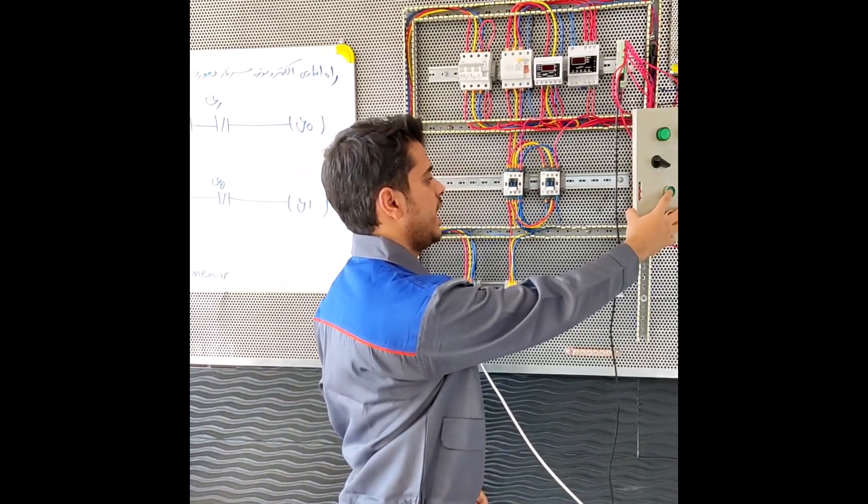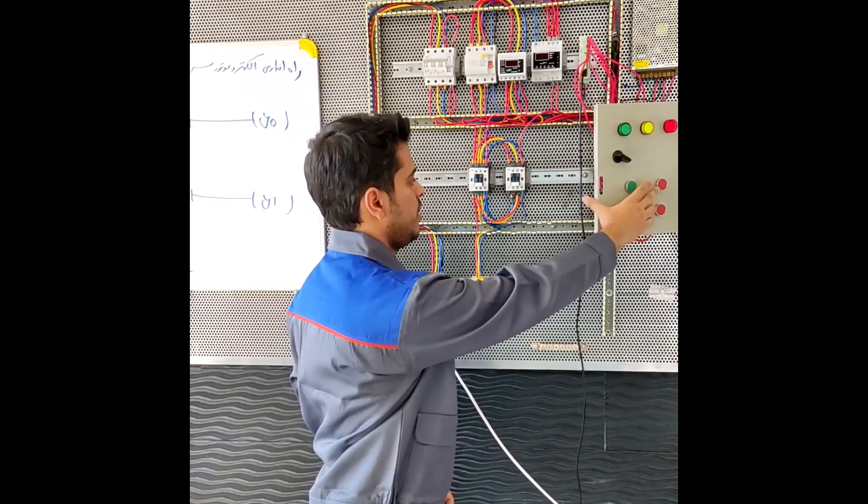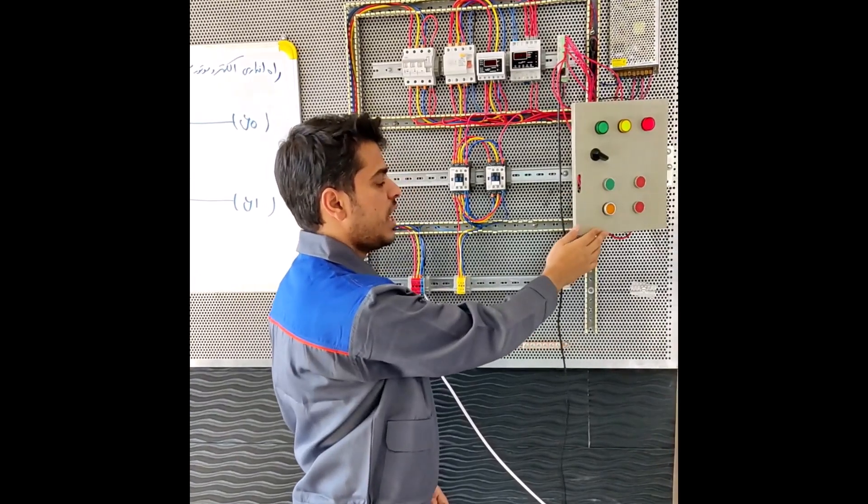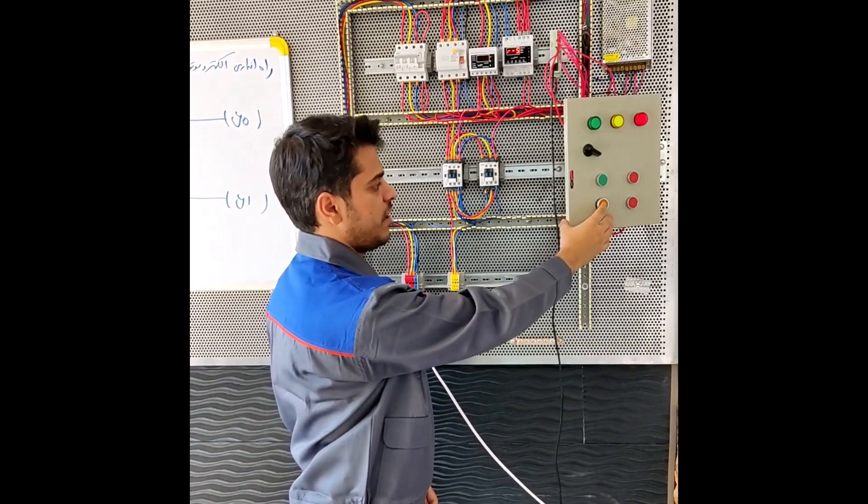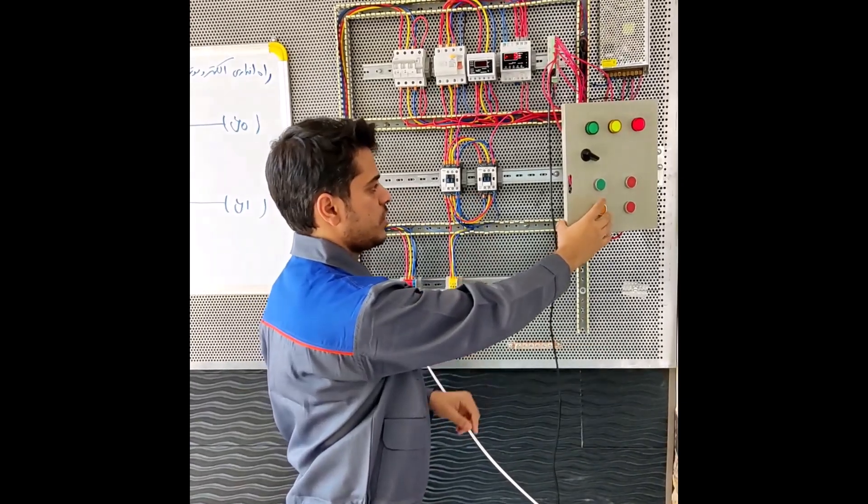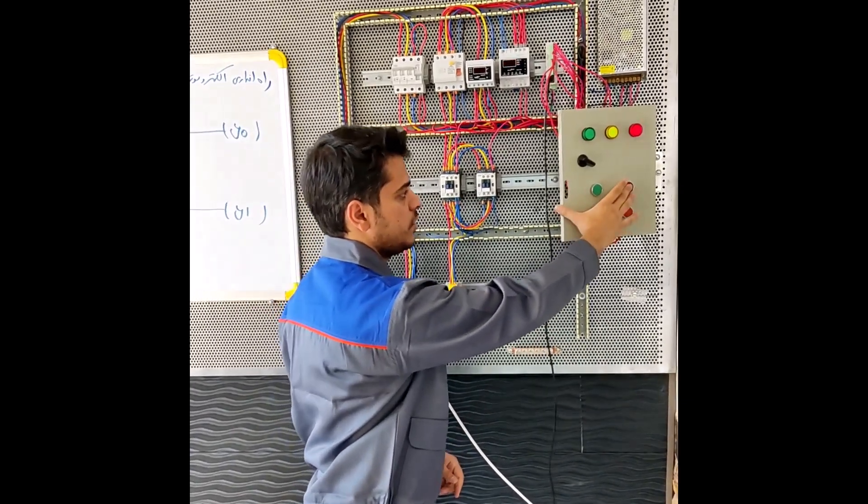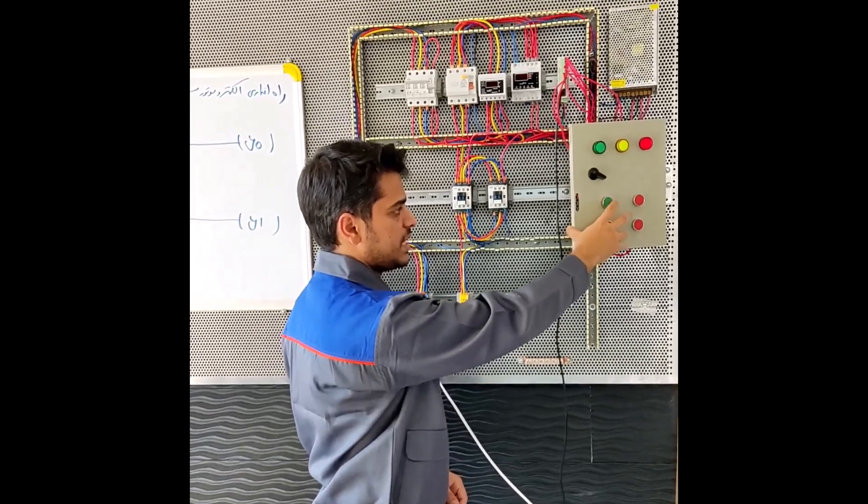This program should not be used for heavy motors. In heavy motors, the stop input must be activated first and the motor shaft must stop completely, and then start in the other direction.